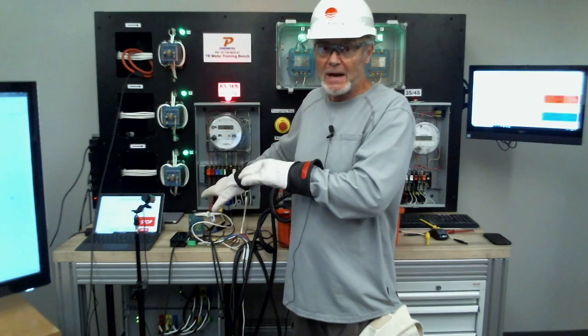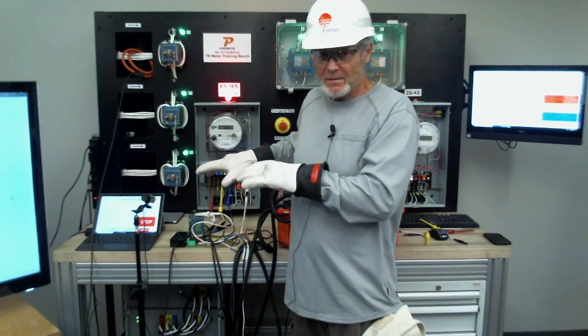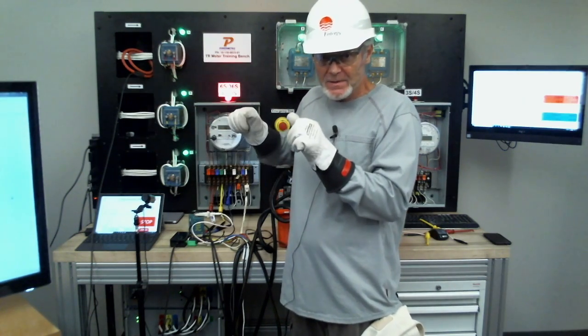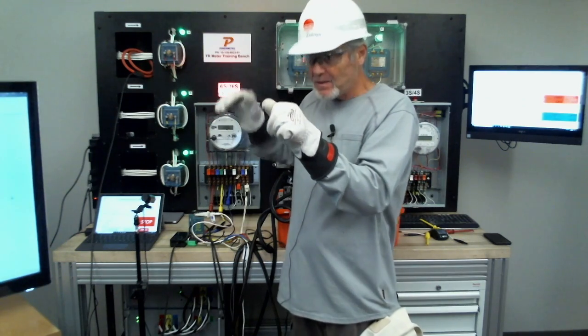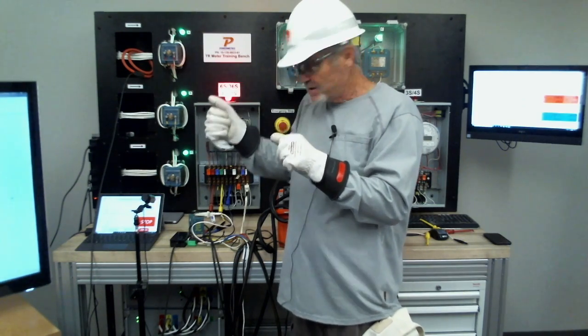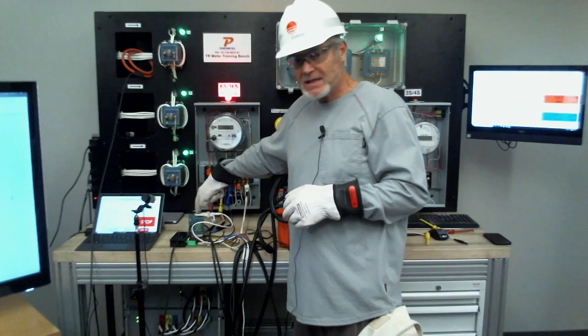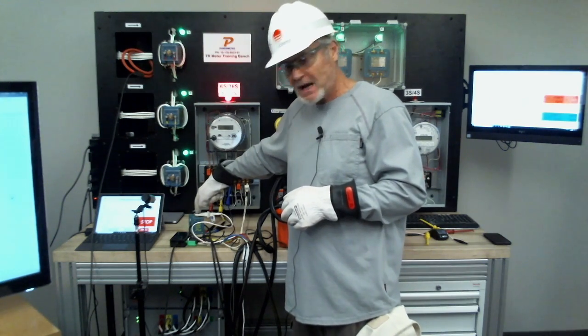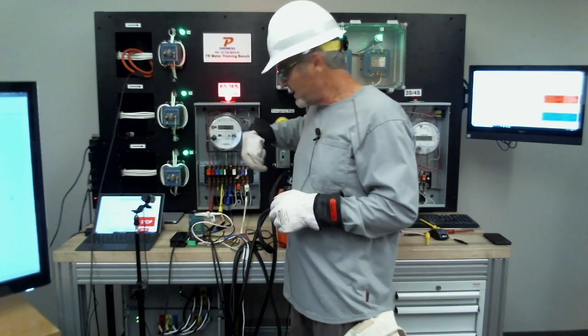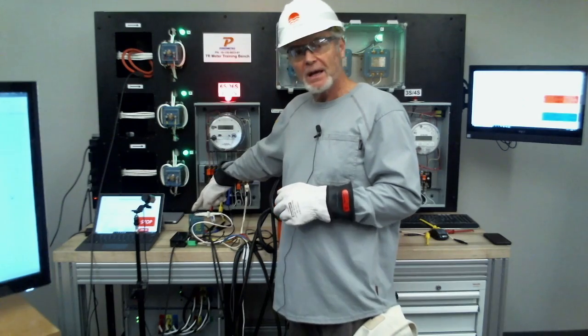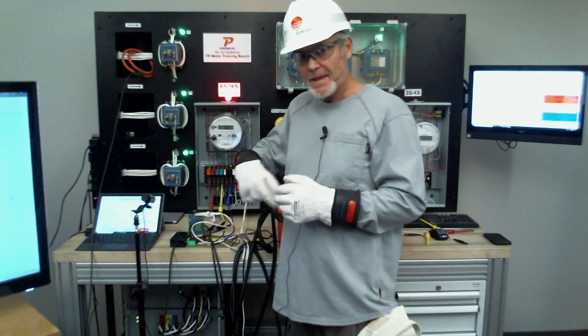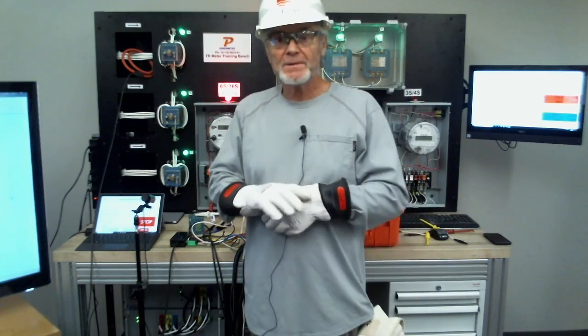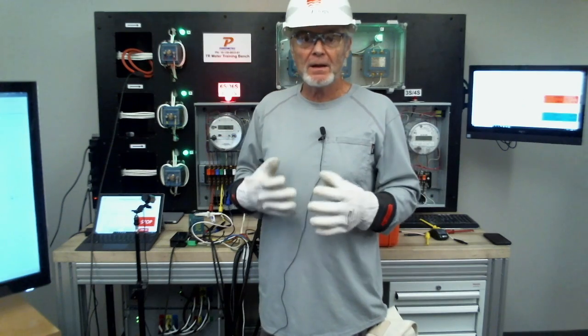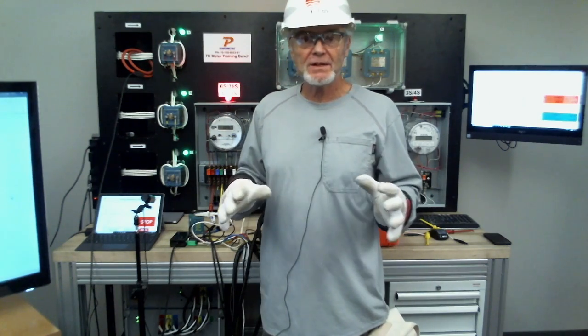you're measuring now, you're not driving. Okay, and you don't have duckbills anymore, so you're going to have to use the alligator clips. So the white alligator clips the in, the black alligator clips the out. So you just see where it's coming out of the dot side of the secondary of that CT for a bench top, and that comes in the white into the kit, and then the black comes out of the return, completes the circuit for you. Okay? Hope this helps. Hope everybody got to see the connections really well. If you have any other questions, please holler at us.